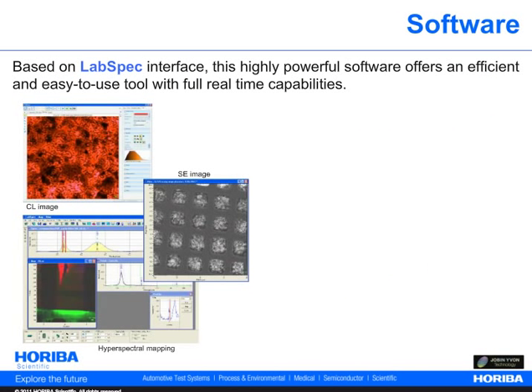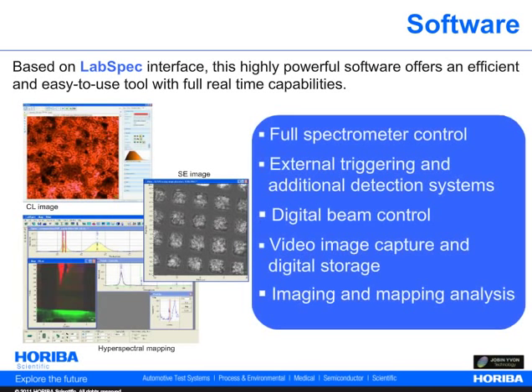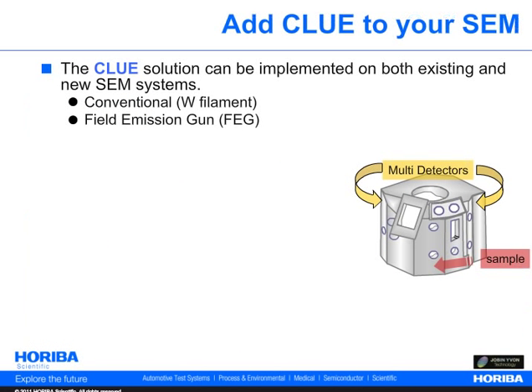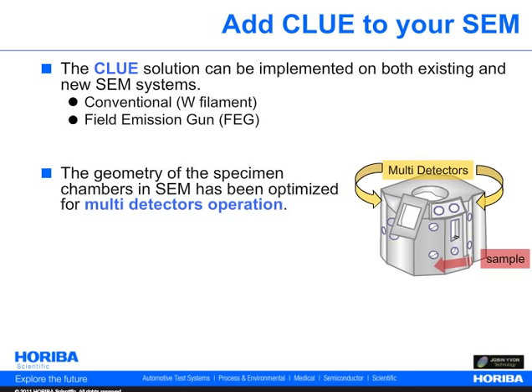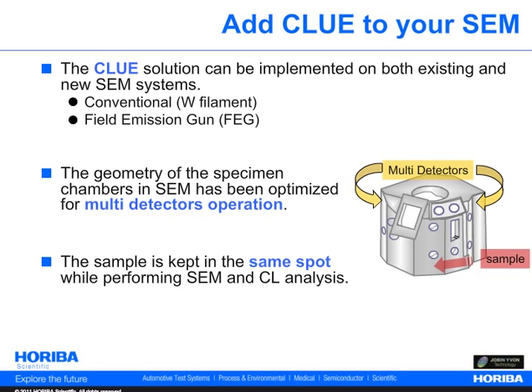The CLUE series is driven by the LabSpec software. The software features comprehensive system control and advanced data acquisition routines for CL measurement and sample mapping. A large variety of advanced imaging functions and spectral analysis provides the versatility and performance required to analyze a large range of CL applications. The CLUE packages are all compatible with conventional or field emission SEM and can be implemented on both existing and new SEM systems. The SEM chamber enables attachment of the CL probe to one of its horizontal ports, and the sample is kept in the same spot while performing SEM and CL analysis.